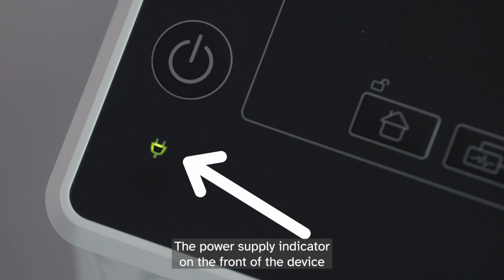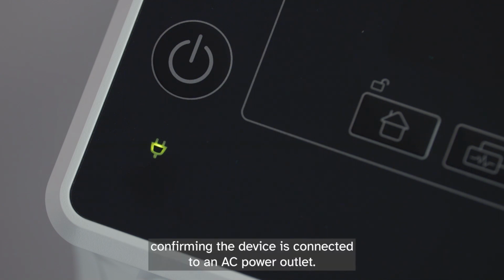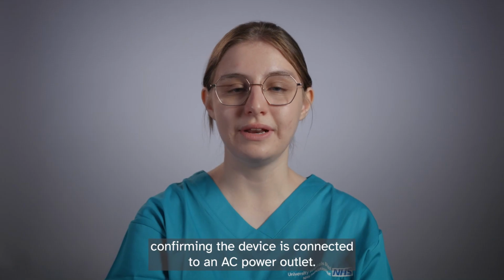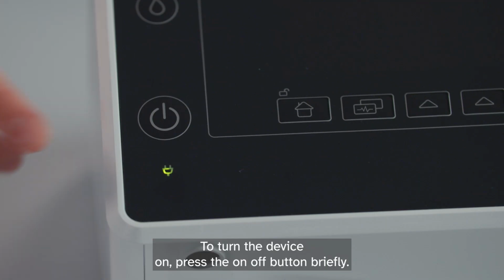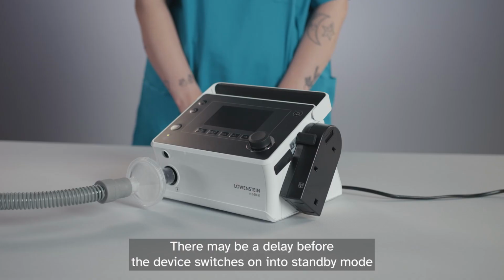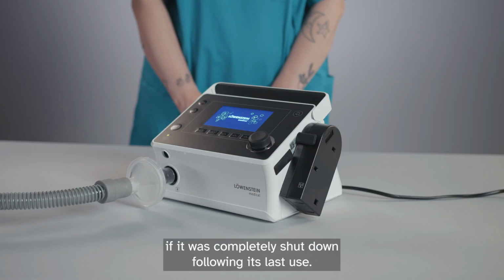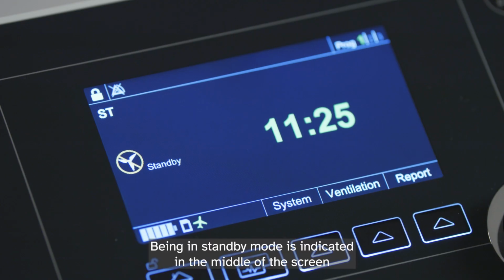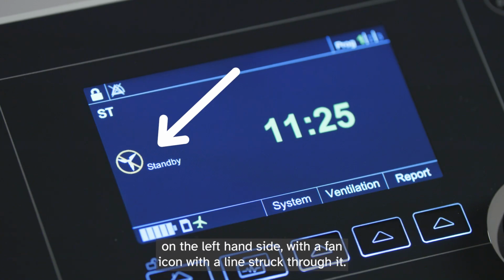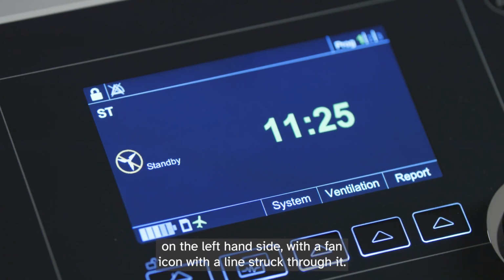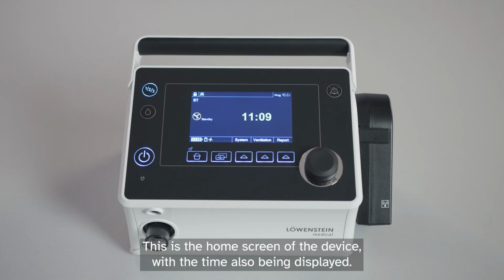The power supply indicator on the front of the device should now be illuminated, confirming the device is connected to an AC power outlet. To turn the device on, press the on-off button briefly. There may be a delay before the device switches on into standby mode if it was completely shut down following its last use. Being in standby mode is indicated in the middle of the screen on the left-hand side with a fan icon with a line struck through it. This is the home screen of the device with the time also being displayed.